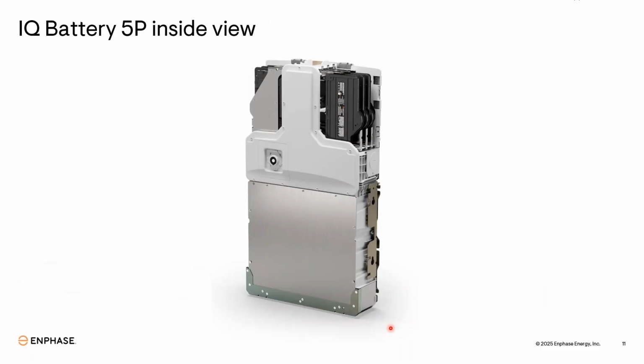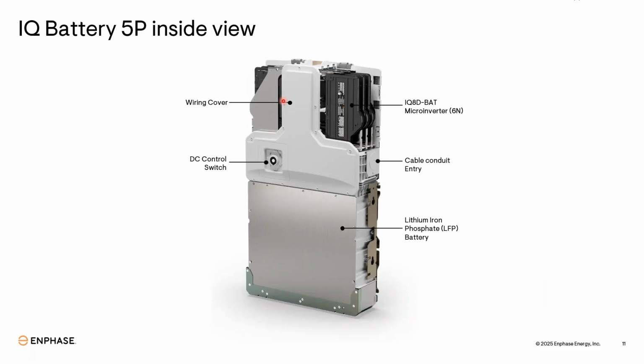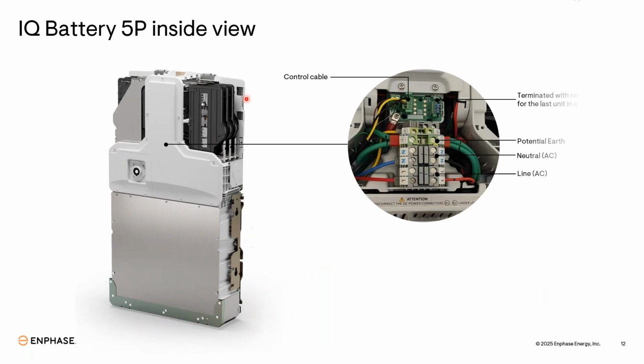This is the inside view of a single phase battery, the earlier version available in India, if you are going for a single phase only. This is the battery stacking. This is the wiring cover. These are the DC buttons. These are the microinverters, 6 microinverters inside this battery. The model is IQ8D BAT. So 3 this side, 3 opposite side. If you see the wiring, you need to remove this wiring cover. Inside it, you will see this type of connection. Simple: line, neutral, earthing, and communication cable. You need only this connection to connect with your system controller. So this is the single phase battery, the earlier, older model available in India.